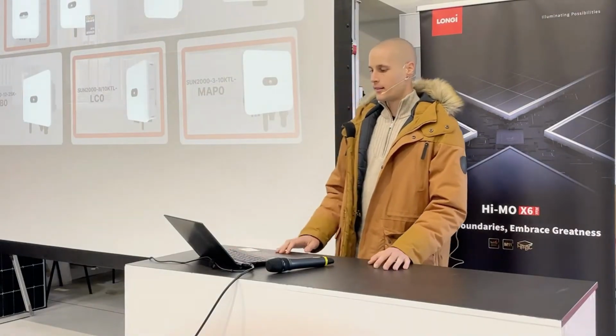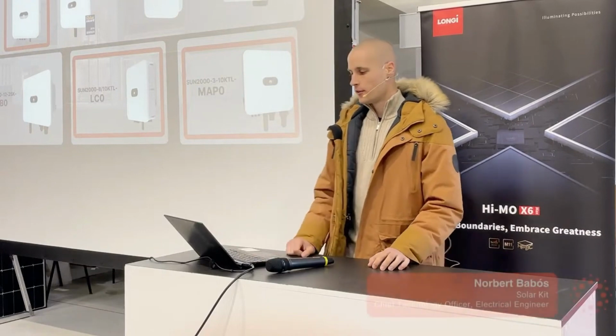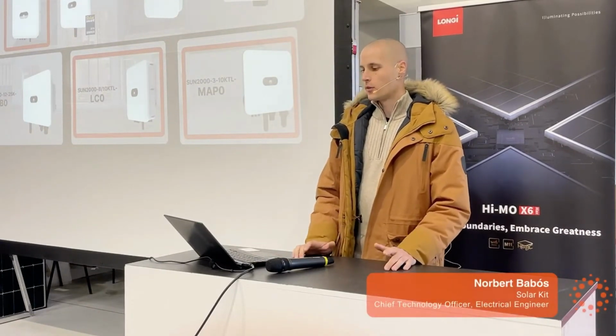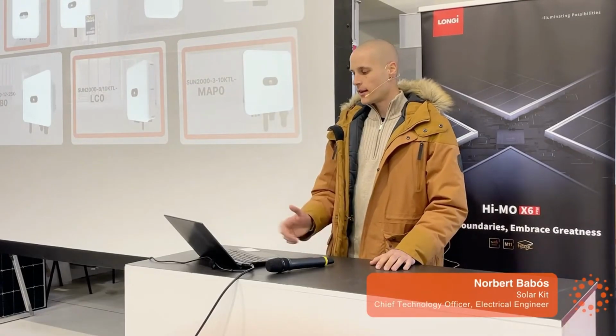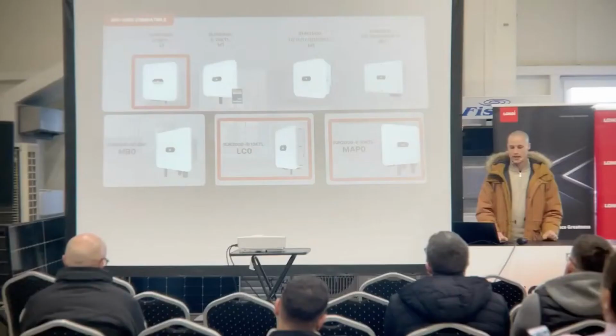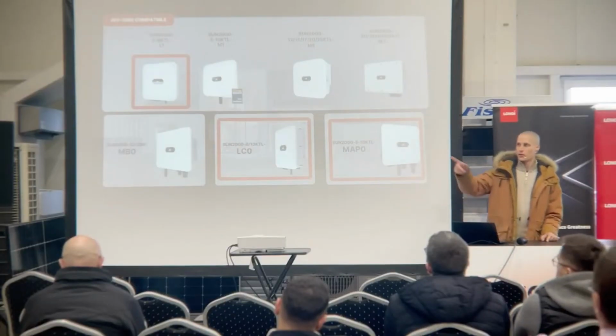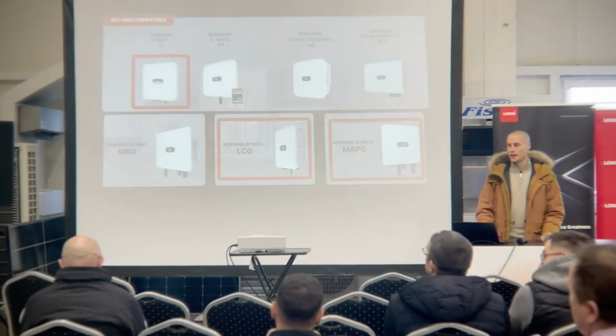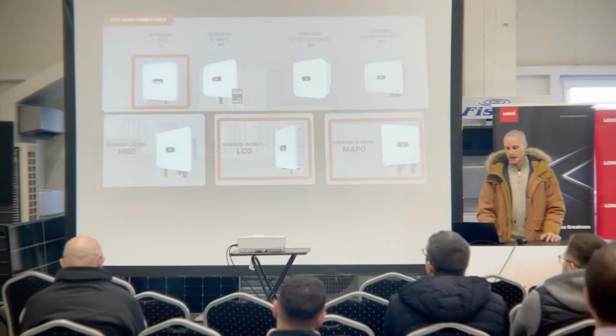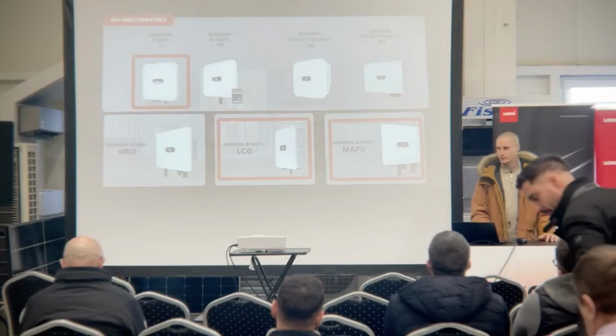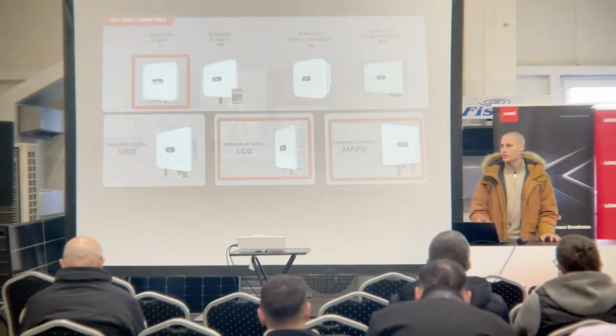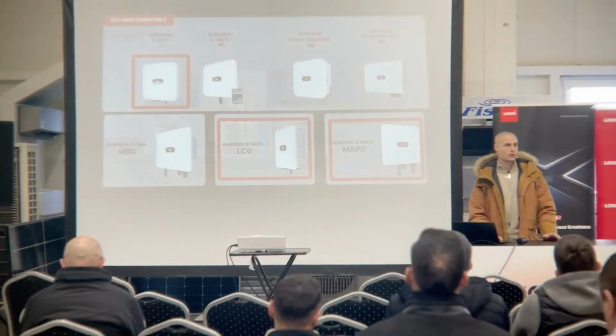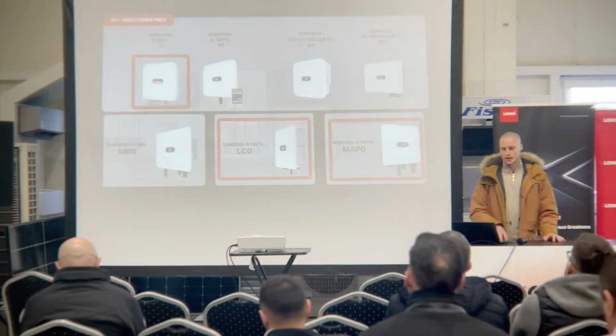So let's begin with Huawei. As you know, Huawei has right now 3 brands, 3 families that can work in pure off-grid mode. From single phase, it's the L1 and the LC0, which is the new one. The L1 ranges from 2 to 6 kilowatt on single phase, and the LC0 ranges from 8 to 10. The LC0 is that one in the middle of the house, an 8 kilowatt single phase inverter. From 3 phase is the new MAP0, which we don't have displayed, but it's the next generation of the M1. So these 3 types of inverters can work in pure off-grid mode.